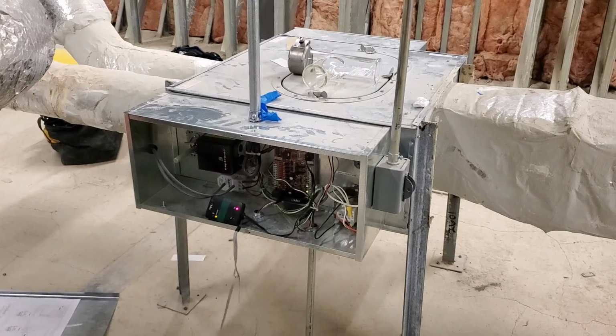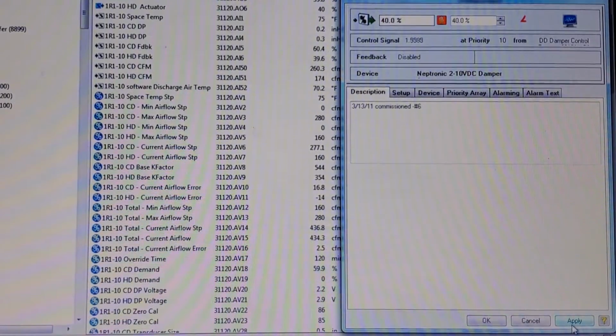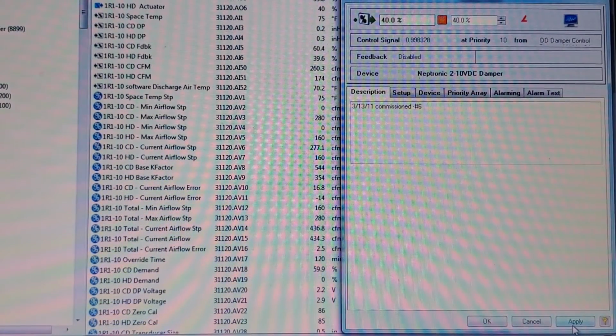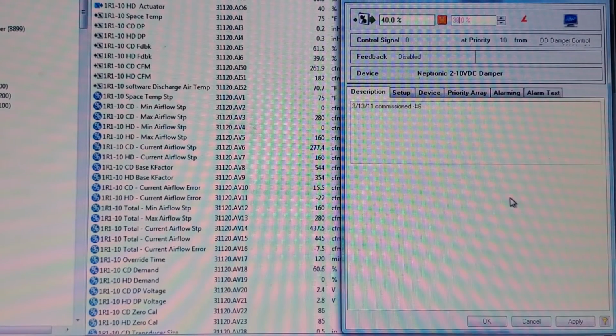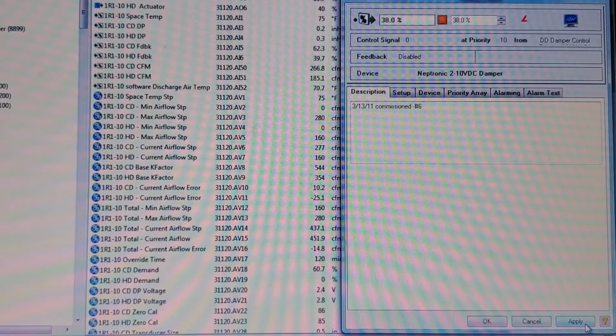Alright, so once you're connected, you can log in, and you should see this screen depending on the control software that you're using. So in this case we have a dual duct, but what we're going to be doing is we're going to calibrate the hot deck side of it. And actually on this project they want us to calibrate the min and max, but for this example we're only going to be calibrating the max side of the unit, which is pretty typical for any job.